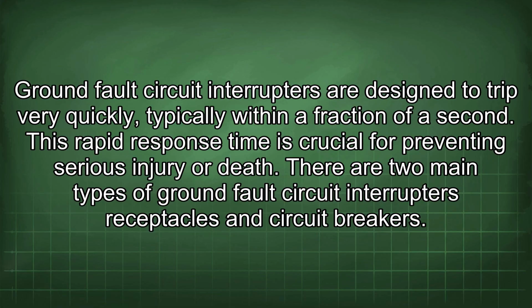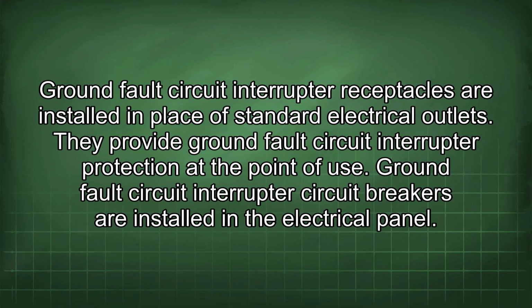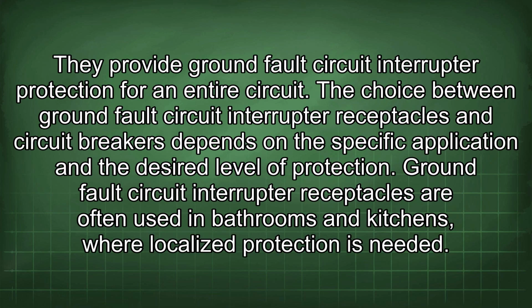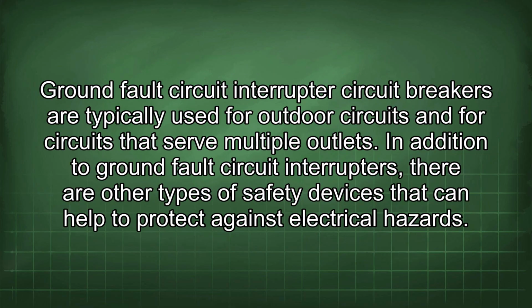There are two main types of ground fault circuit interrupters: receptacles and circuit breakers. Ground fault circuit interrupter receptacles are installed in place of standard electrical outlets. They provide ground fault circuit interrupter protection at the point of use. Ground fault circuit interrupter circuit breakers are installed in the electrical panel. They provide ground fault circuit interrupter protection for an entire circuit. The choice between ground fault circuit interrupter receptacles and circuit breakers depends on the specific application and the desired level of protection. Ground fault circuit interrupter receptacles are often used in bathrooms and kitchens, where localized protection is needed. Ground fault circuit interrupter circuit breakers are typically used for outdoor circuits and for circuits that serve multiple outlets.